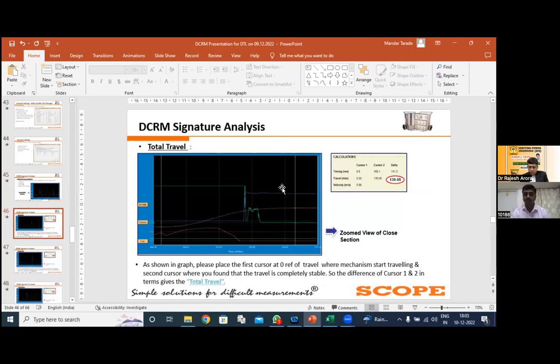For total travel, at the time of explaining you need to place the cursor where your mechanism is steady, where your mechanism is idle. There is no movement in the mechanism, or your coil energization just begins. Once your plunger hits, the latch will get released and the mechanism will start moving. The first point is where your mechanism is at the 0th position, so we keep our cursor at the first position there. And the second, where your mechanism is completely steady. The delta between these 2 points gives you the idea of your total travel.